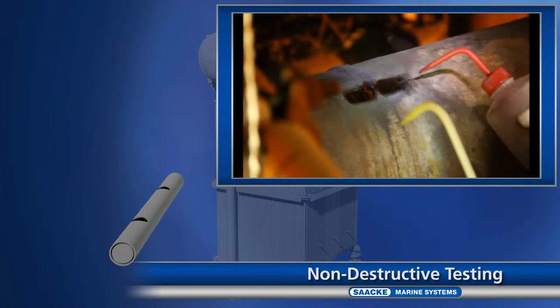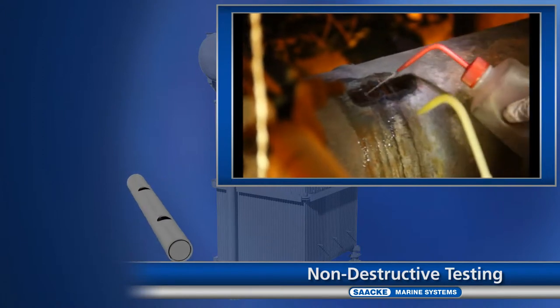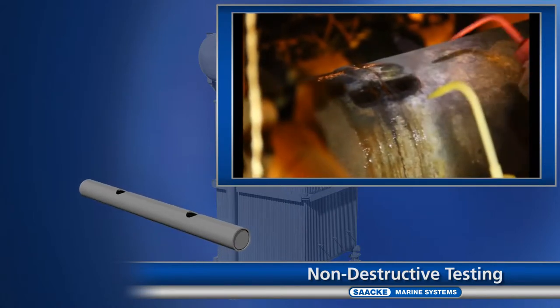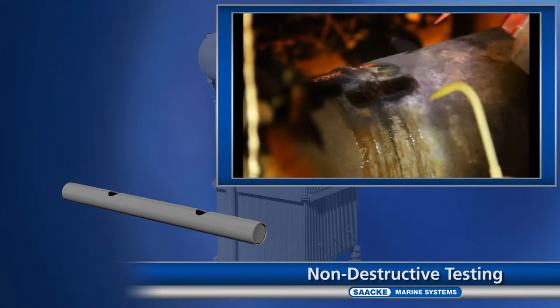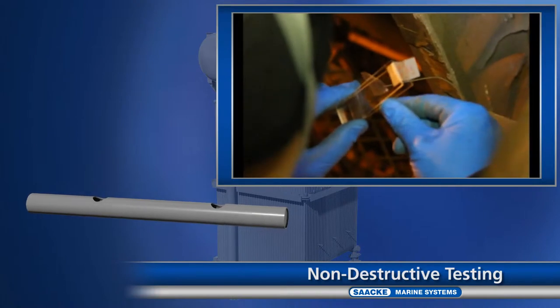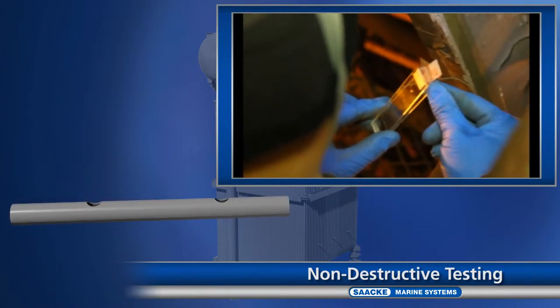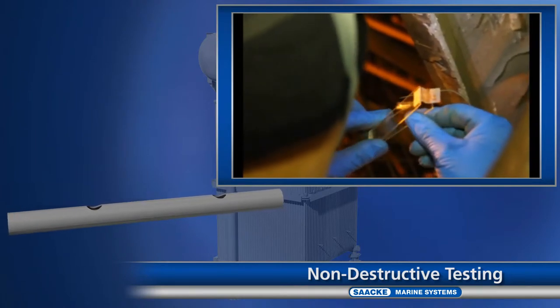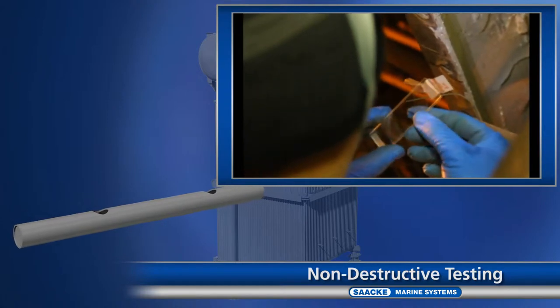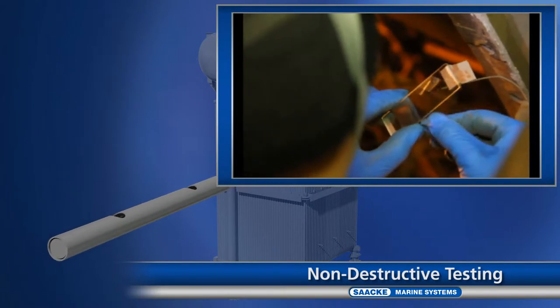In a non-destructive inspection, as here in the case of a steam header, the existing elements are checked for their further usability and descaled. In cooperation with the classification societies and future operators, the components that will no longer be used are removed, while the remaining ones are refurbished and checked again. Saacke makes use of all commonly applied methods, from structural analysis and ultrasonic testing all the way to magnetic particle tests.